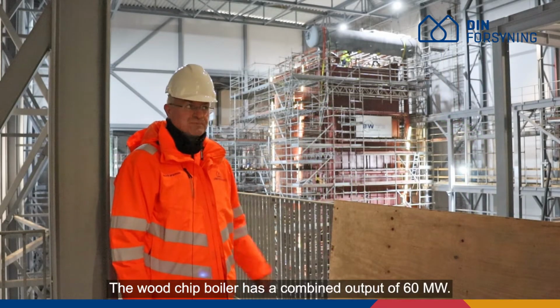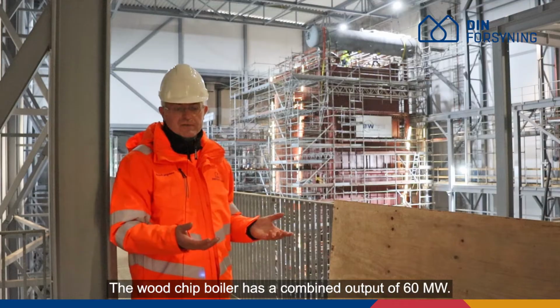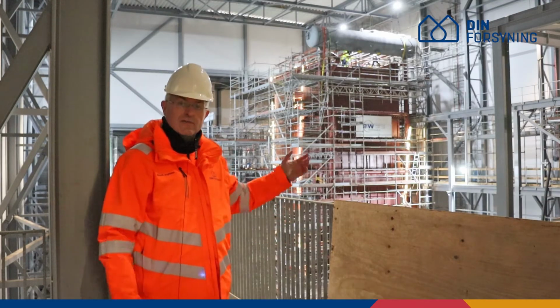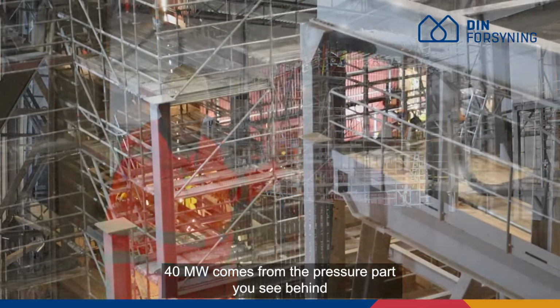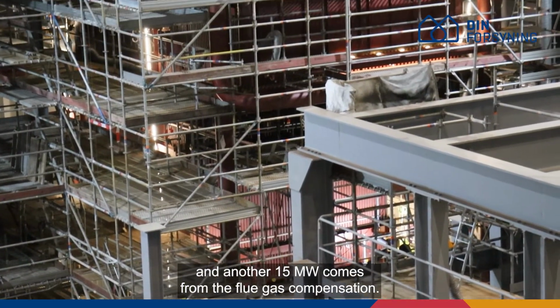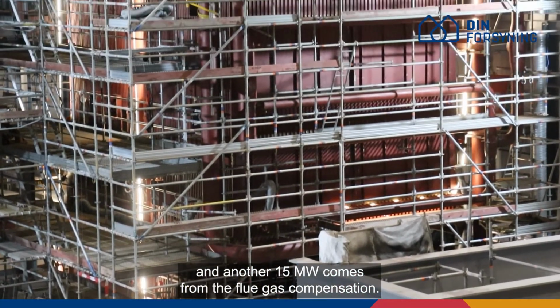The wood chip boiler has a combined output of 60 megawatt. 40 megawatt comes from the pressure part you see behind, and another 15 megawatt approximately comes from the flue gas condensation.